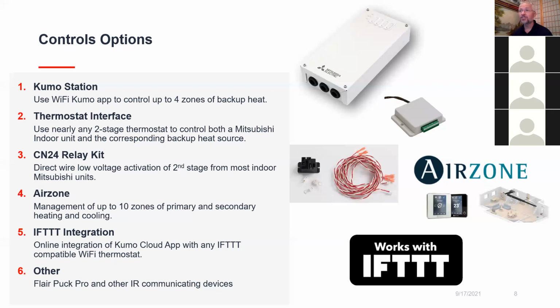Third option is a CN24 relay kit. Most of our equipment, with some exceptions, has a CN24 port on the control board of the indoor unit. It's two pins, and anytime the system needs to call in the cavalry, and this happens whether you connect something to it or not, all the systems you've installed that meet these criteria have those two pins. Those two pins light up with 12 volts DC, 0.1 amps, anytime it's unable to keep up.